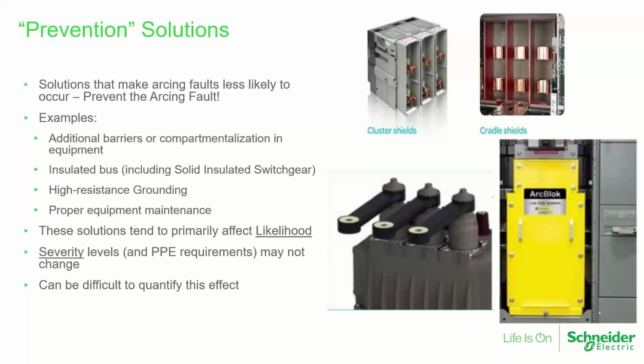We're starting to see more and more innovations in this area. But sometimes it's as simple as putting additional barriers or compartmentalization in equipment. Maybe making it harder to drop a tool into energized bus or something like that. Sometimes it may be using insulated bus, including solid insulated switchgear, gas insulated switchgear. Air insulated switchgear is fine. It's been around for a long time, but may not offer you some of the protections that some of these other alternative methods do.